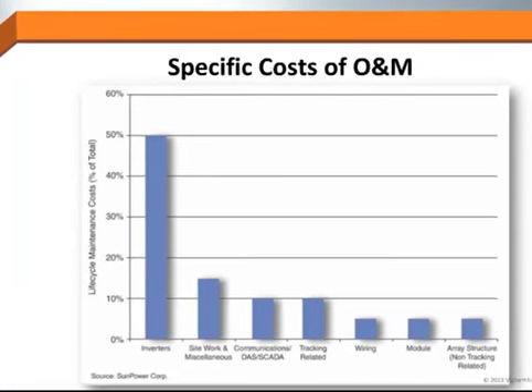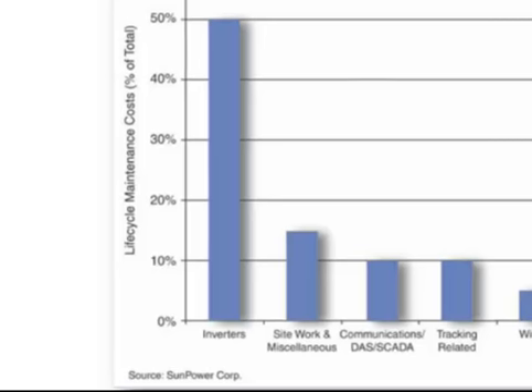This data shows that inverters are responsible for about 50% of the cost of O&M over the lifetime. So if you didn't know, inverters are the culprits. They're very expensive pieces of machinery, and they're under a lot of environmental strain. They're out there in the hot sun, or in a box in the hot sun, trying to survive, with a lot of power going through them, and there are all kinds of ways they can fail. Even if the manufacturer is really good, you can have problems over the lifetime.